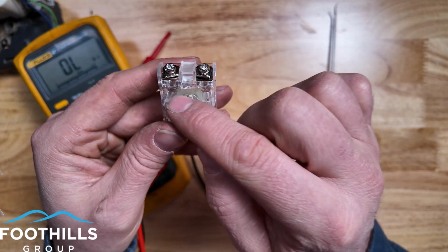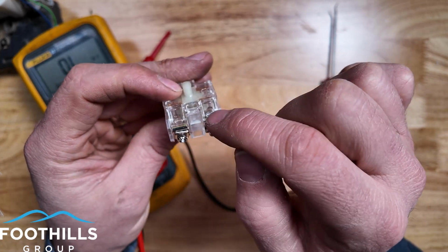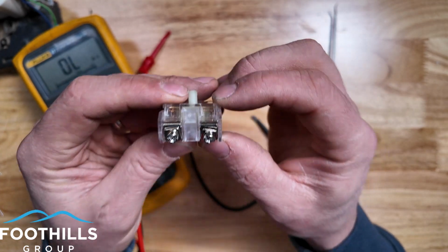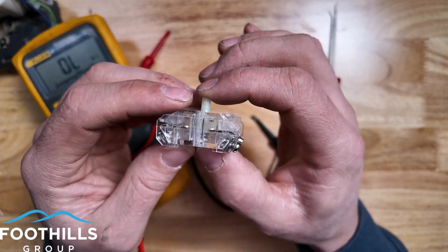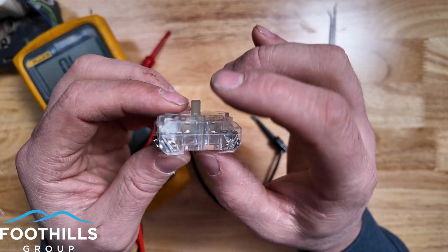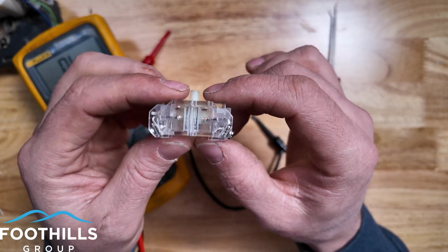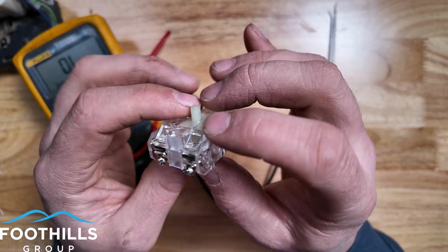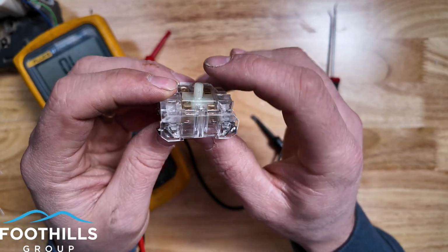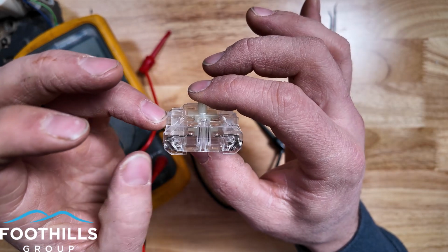And what'll actually happen is it'll start to generate heat in the switch, and it'll actually start to melt these plastic switch bodies. And that's one of the reasons why our switches are rated to a voltage and an amperage, is they can only handle so much heat before they start to melt. So we need to know what the switch is so we can know how to test it. And then once we test it, we need to know what those results actually mean.